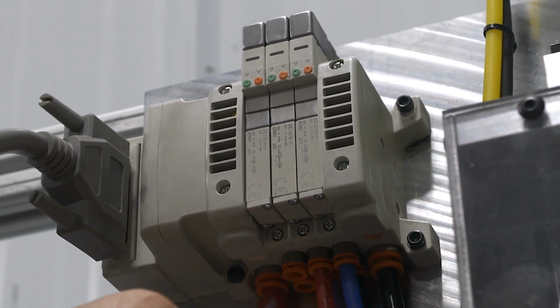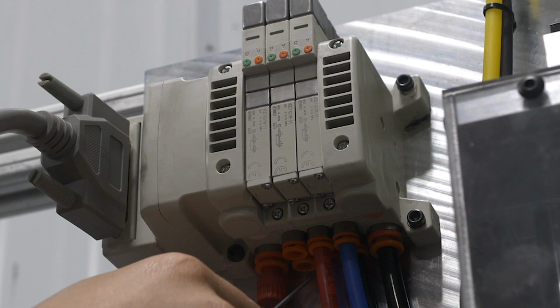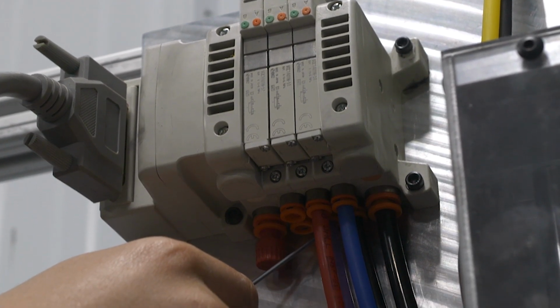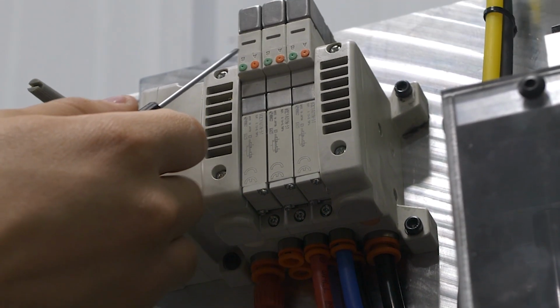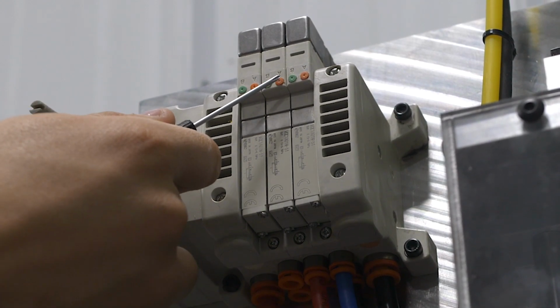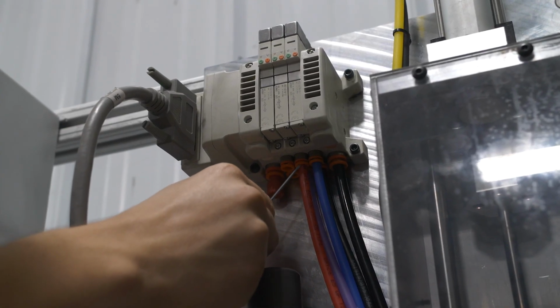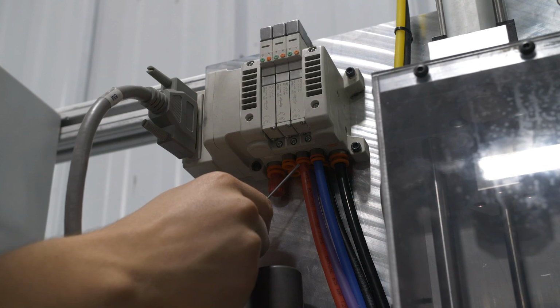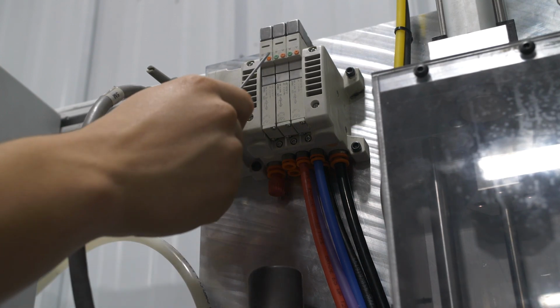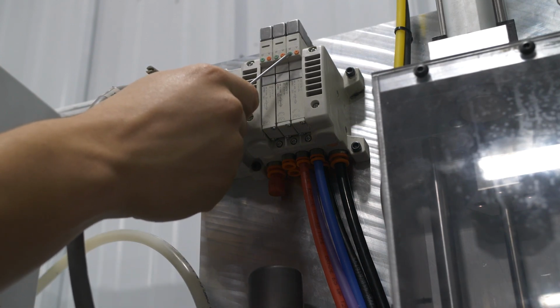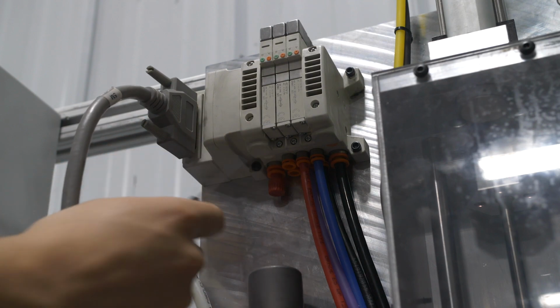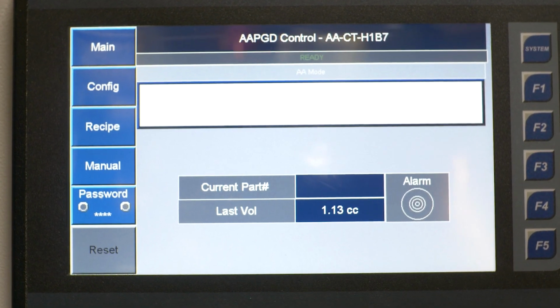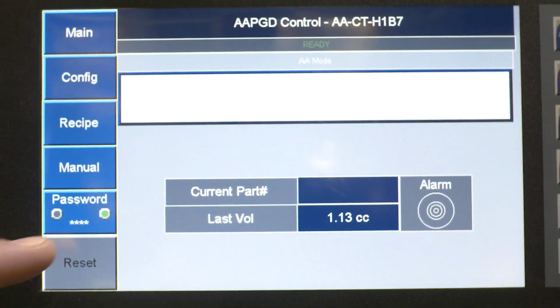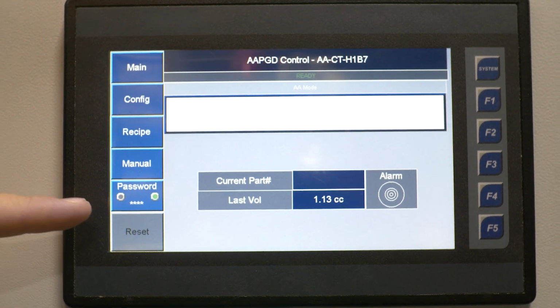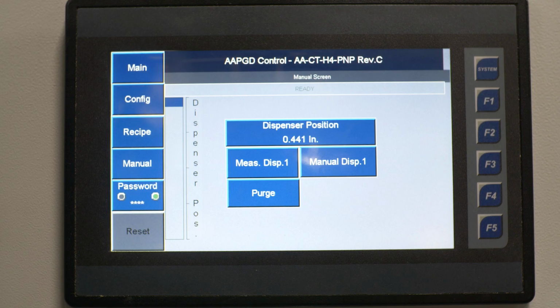If it goes into the bottom or back of the valve stack, like the purple one, that corresponds to the A on that card. If it comes into the front or the top of the valve stack, like red and blue, that corresponds to the B buttons on each individual card. To start troubleshooting the valves, make sure that your password is entered. You'll see that your password is correct if you see one of these 2 lights light up green. To start, go to the manual screen.